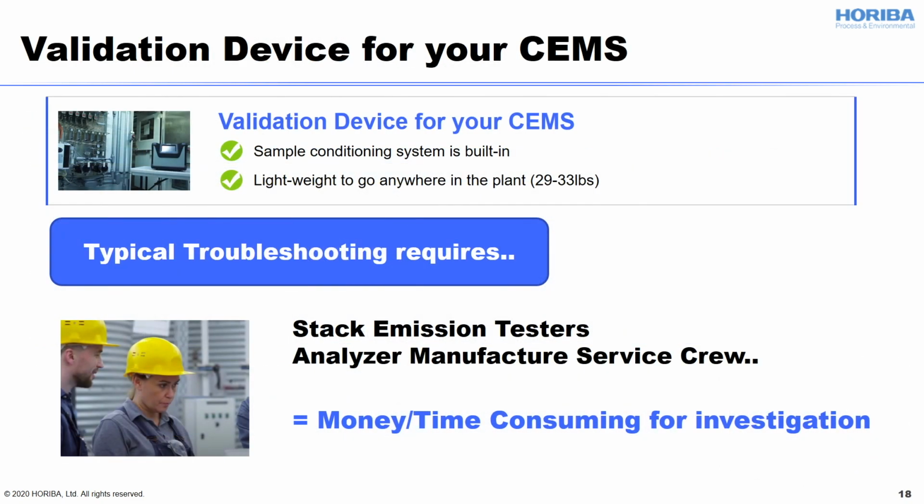Here is another application: a validation device for your CEMS. When you have an issue with your CEMS analyzer, you may need to investigate what happened to it. This troubleshooting often requires third-party investigation, such as stack emissions testers, analyzer manufacturer service crew, or maybe a spare unit. Most of those cases cost money, probably plus a few $1,000s each time. Moreover, it is really time consuming because the trouble may be from the sample gas, the sample gas conditioning system, or the analyzer itself.